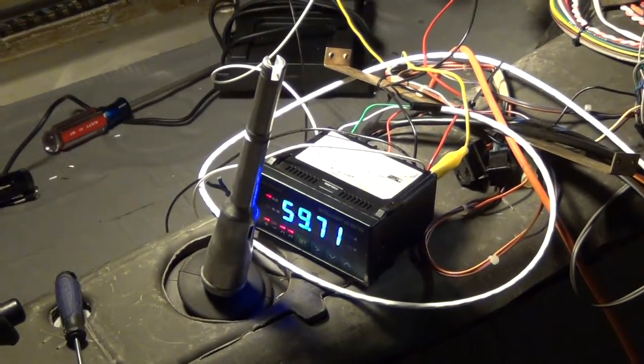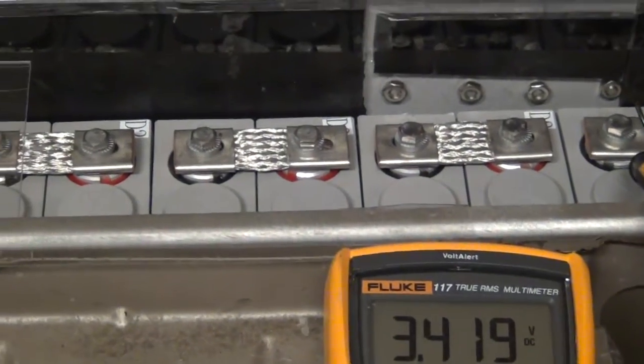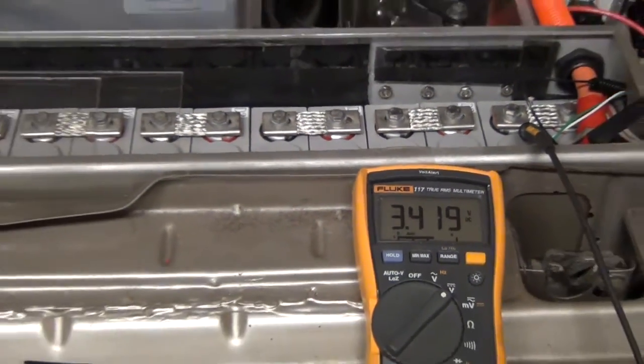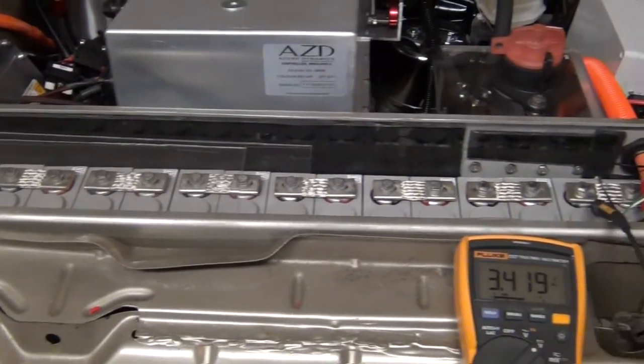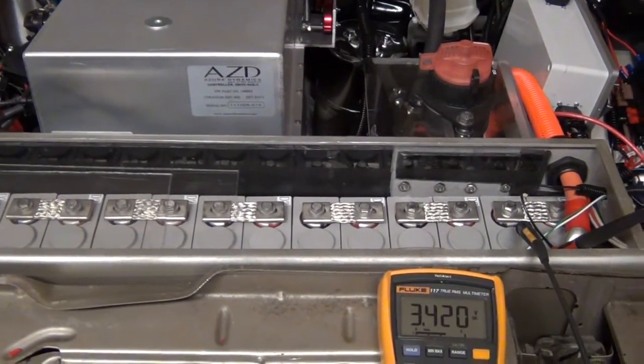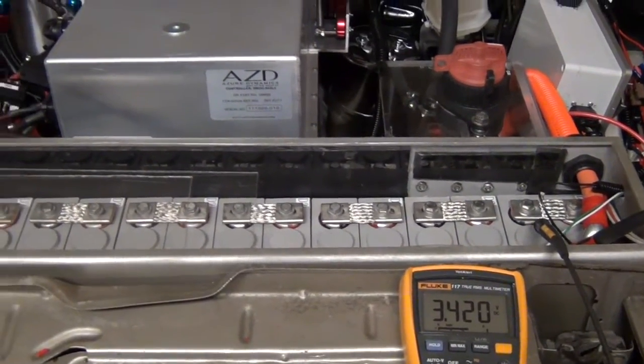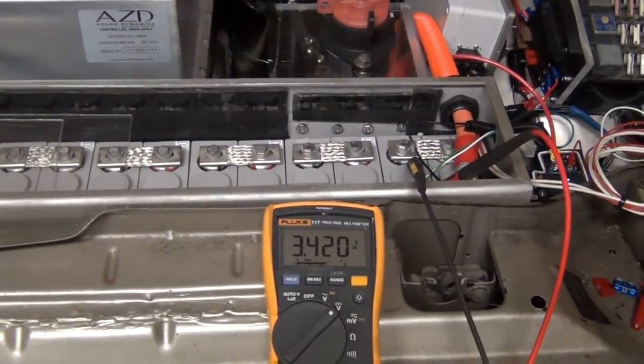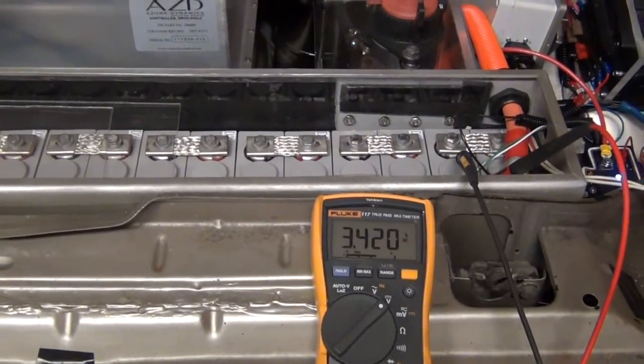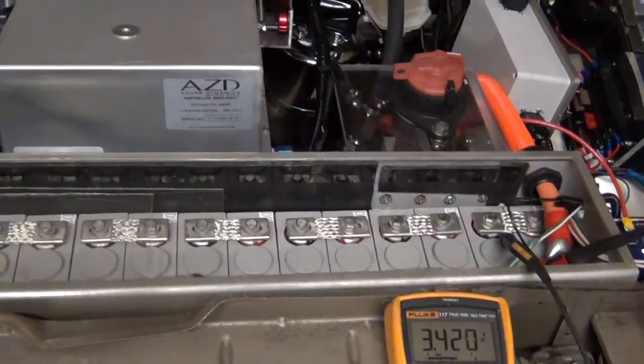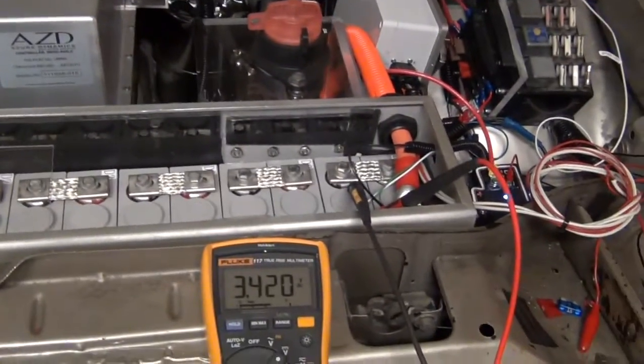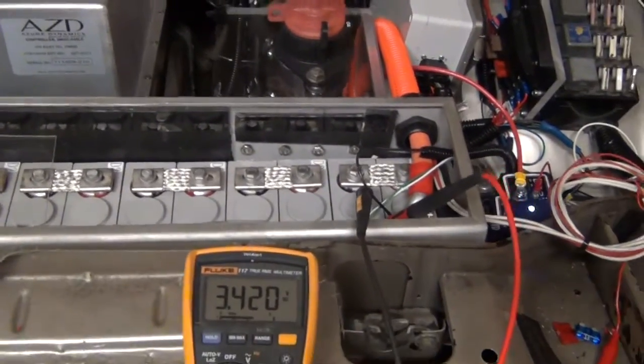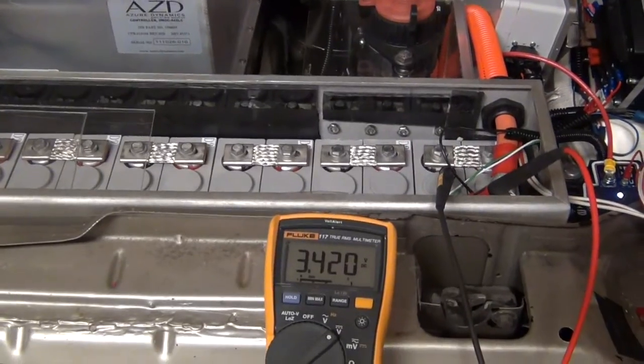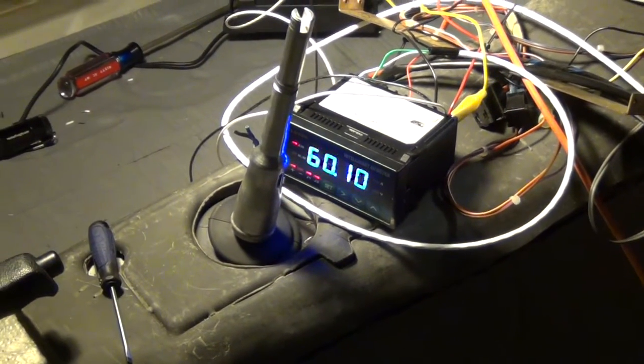Well, almost at 60 amp hours, and looks really good. Most of the batteries are still sitting right around 3.42 to 3.46, so I should be able to get a lot more than 60 amp hours into these batteries, which is what I found on the bench. They usually take about 66, but I think I'll just run it up to maybe something in the mid 60s and leave it at that and see how they settle. Haven't seen anything with any high voltage, which is really good - that means nothing really got damaged. Everything's very close, and I've been measuring the voltage and temperature too, and don't see any hot spots, so it looks really good. There it is, 60 amp hours.